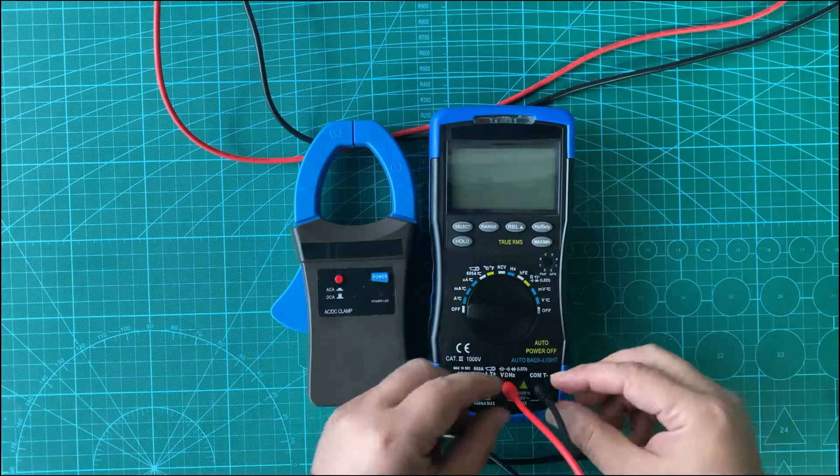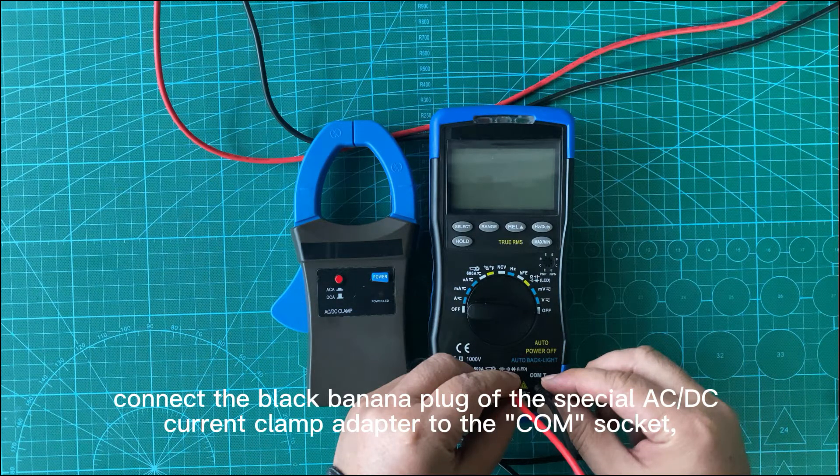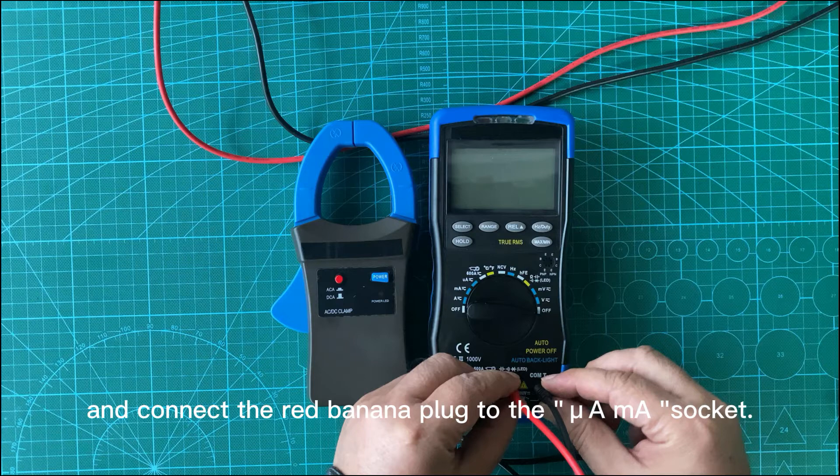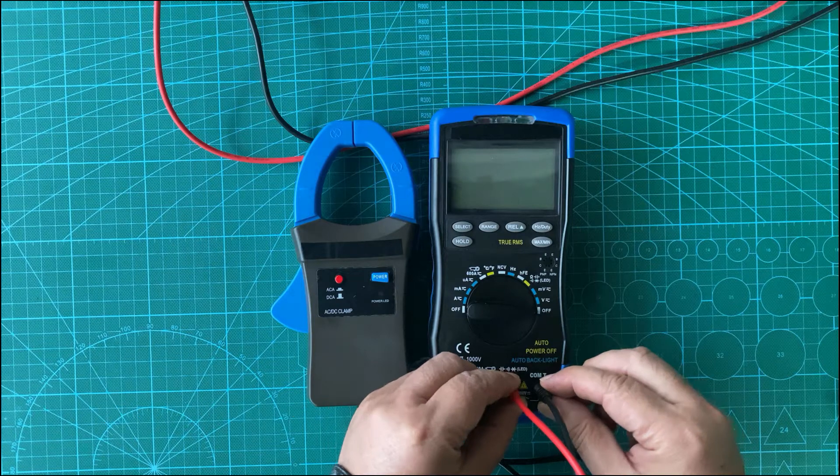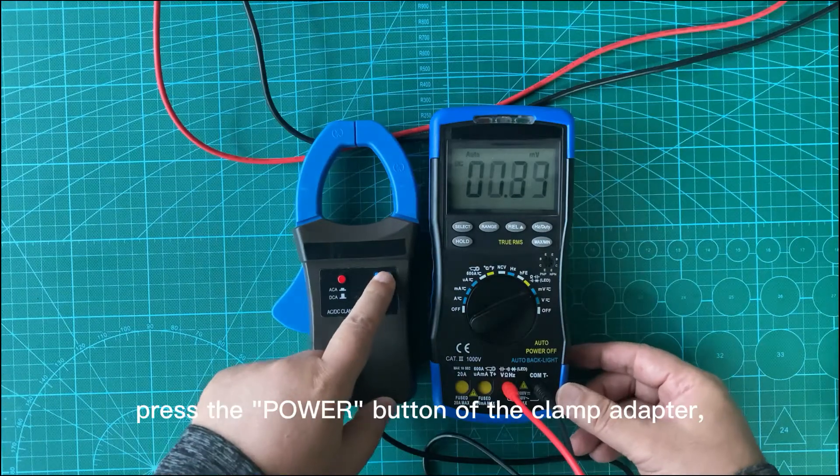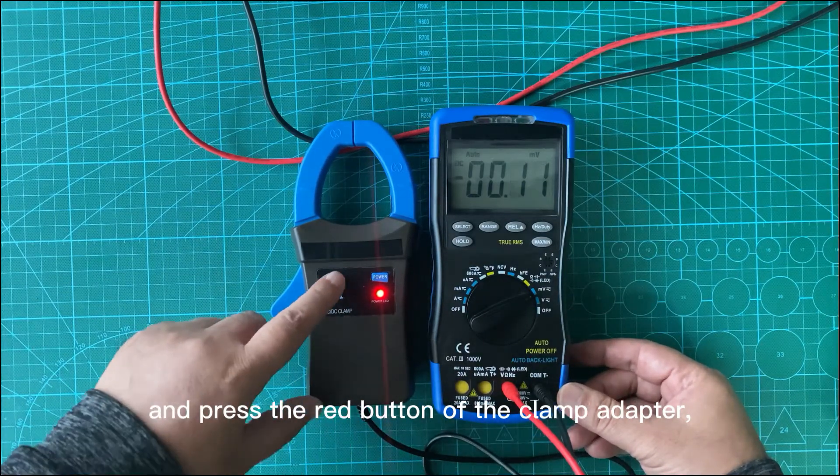AC current measurement. Before measurement, connect the black banana plug of the special AC/DC current clamp adapter to the COM socket and connect the red banana plug to the µA mA socket. Rotate the gear of the multimeter to the mV position. Press the power button of the clamp adapter and press the red button of the clamp adapter.